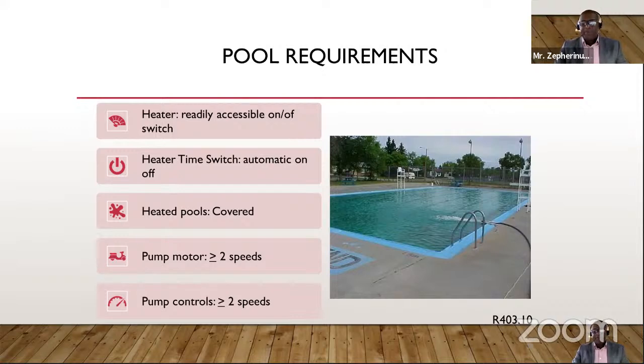When it comes to the pumps and the controls for the pumps, there must be a minimum. The pump must be able to operate at a minimum of 2 speeds or more. The speed is directly proportional to the energy usage. So when you reduce the speed of the pump, meaning that you need a lower turnover of that pump, you're actually saving energy. The implication of not doing that, using a conventional pump, would be that you are using maximum energy all the time when it's not necessary. And the controls as well should be able to control at least 2 speeds or more.